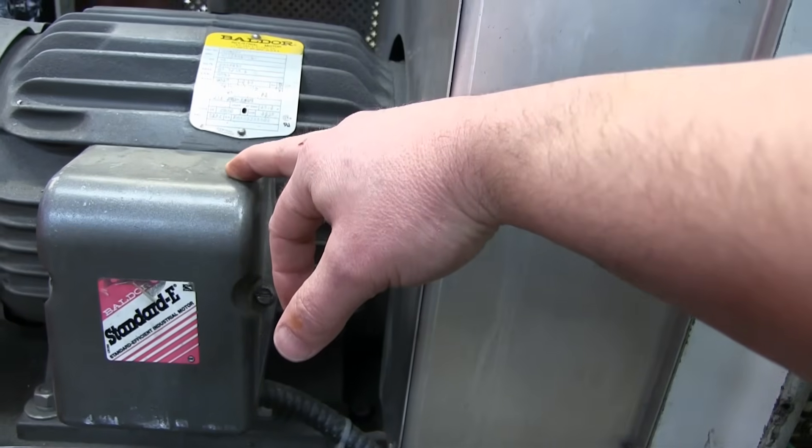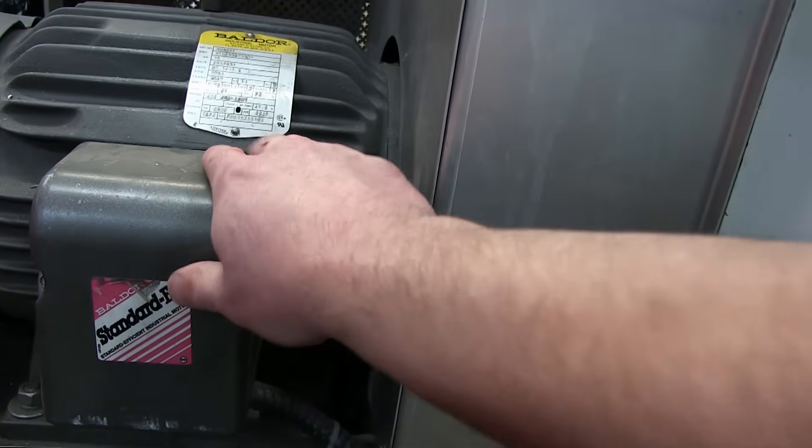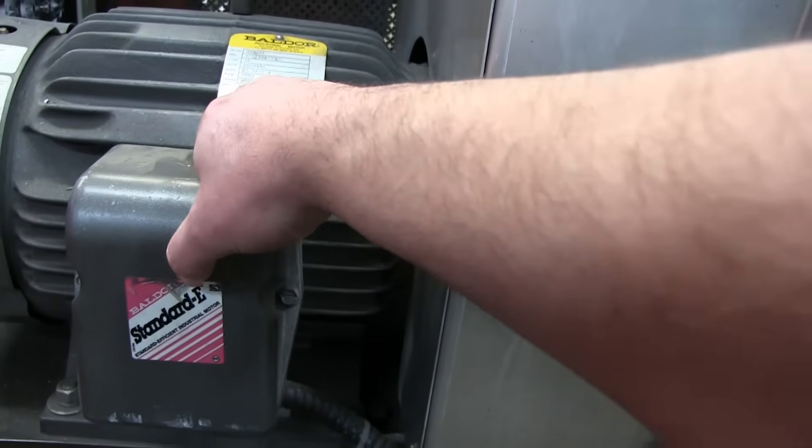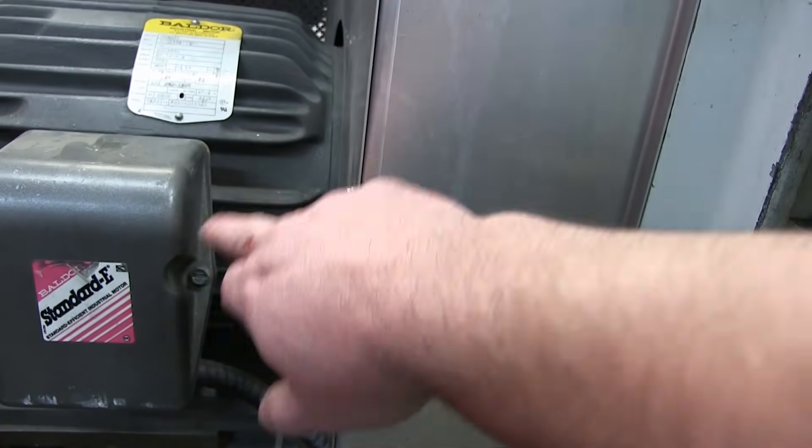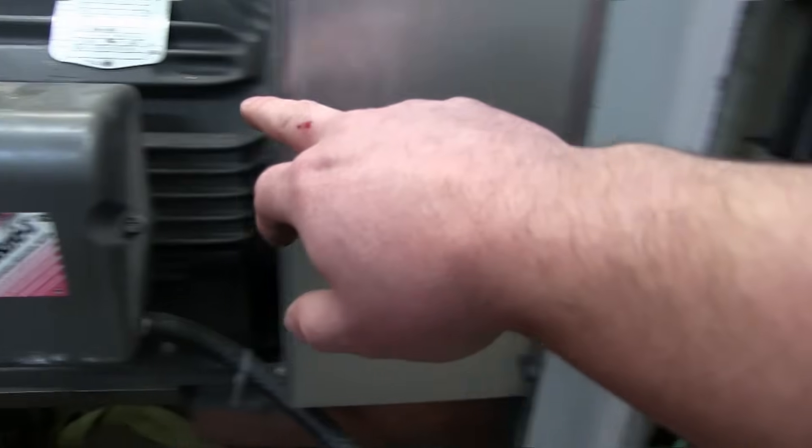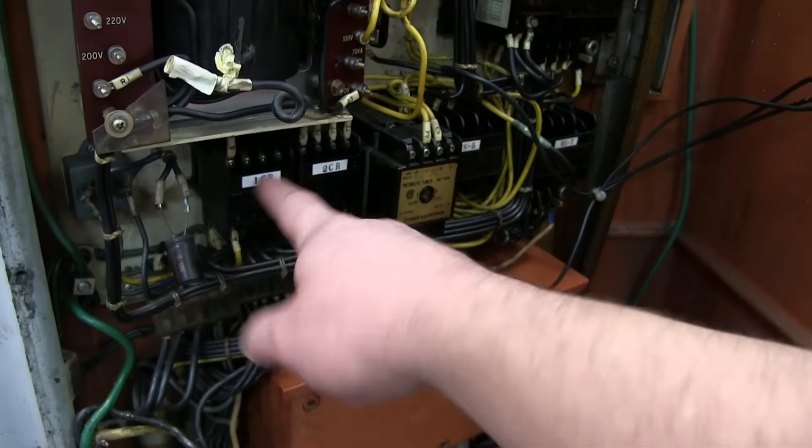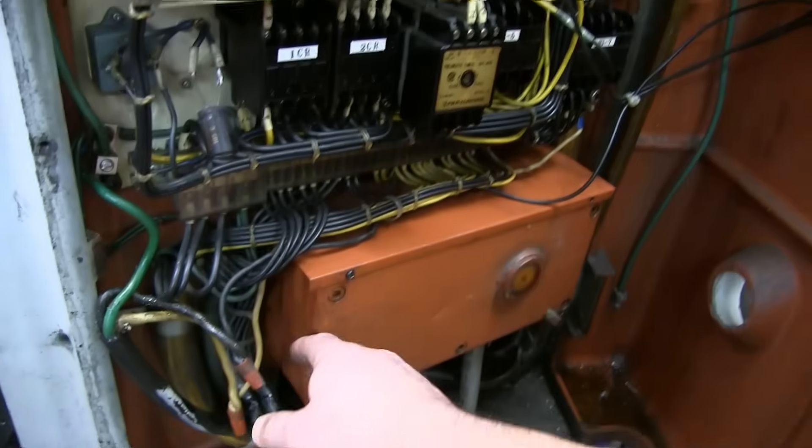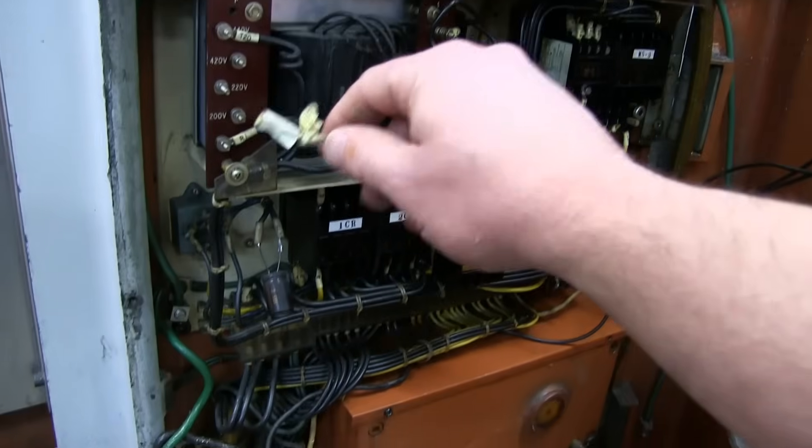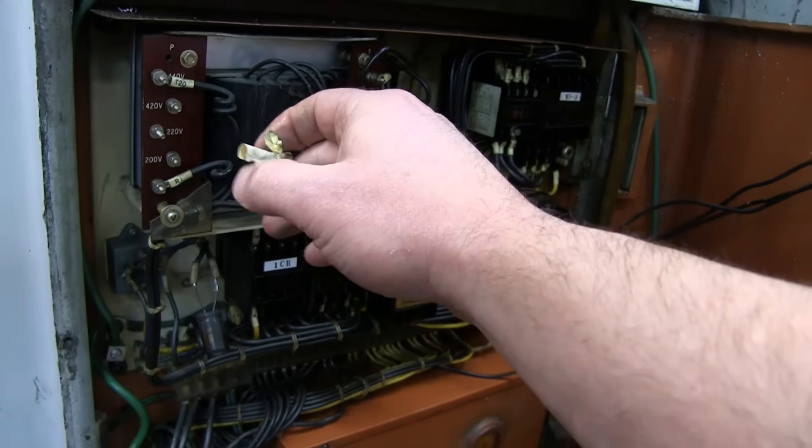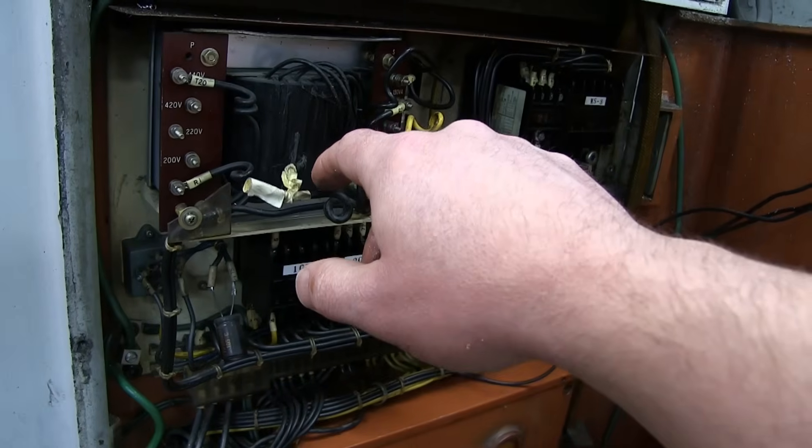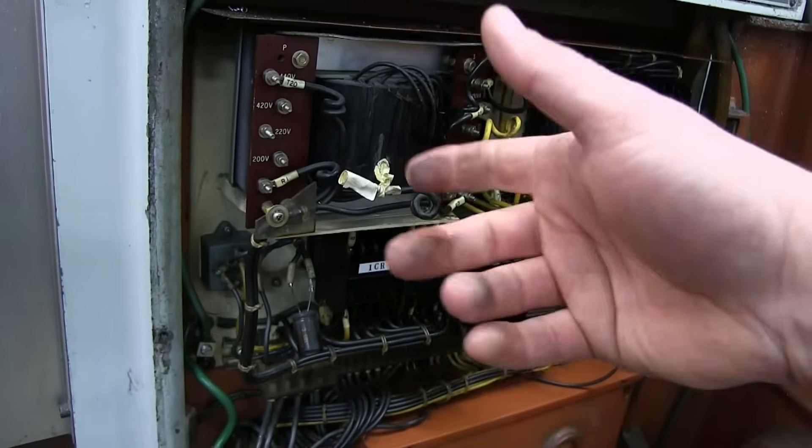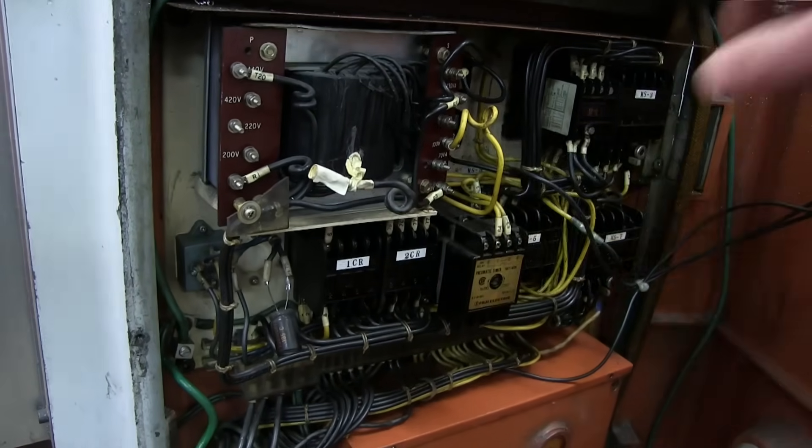Being as how this was not factory, we decided to have a look in here. Old Duclaw, he's just too damn efficient, put the cover back on. But this goes direct to a contactor, so it is not set up on that key switch to change the voltage to low and high voltage. That's why these wires we think are disconnected, and that's why we think they've also disconnected this, so that if it's on 440 volts we don't fry anything in case some button pusher gets in there and switches it over.